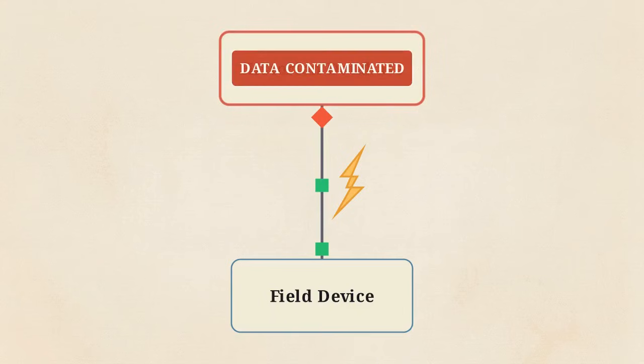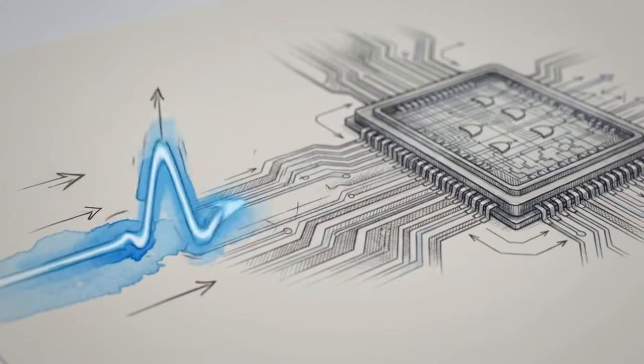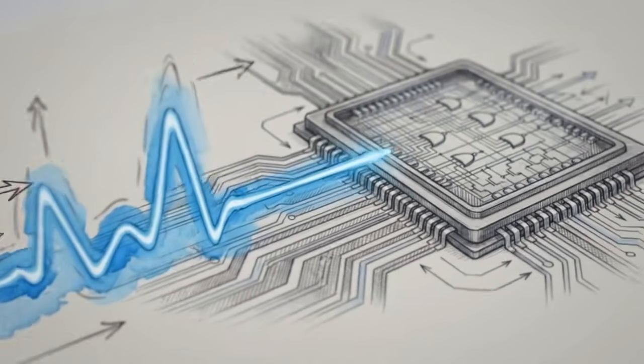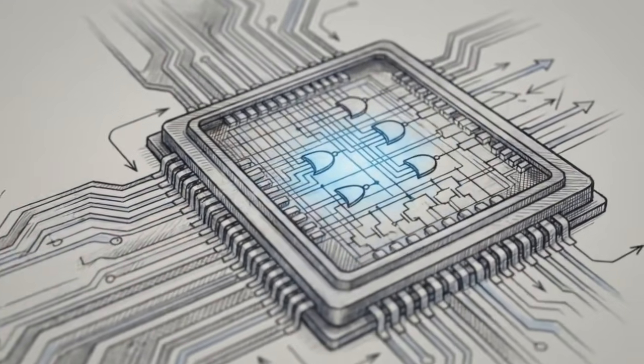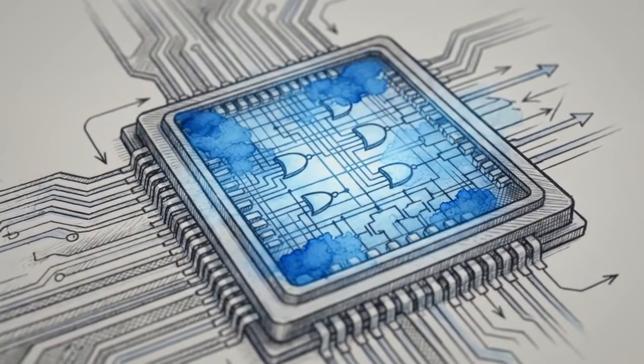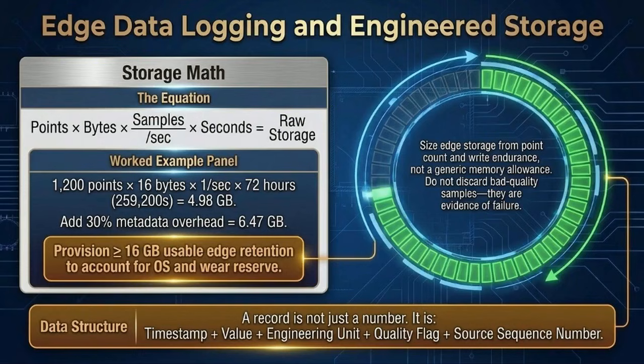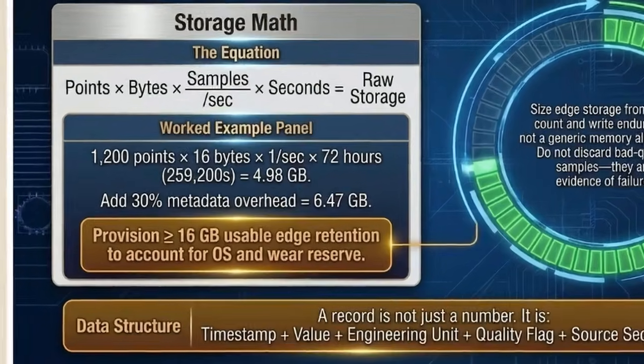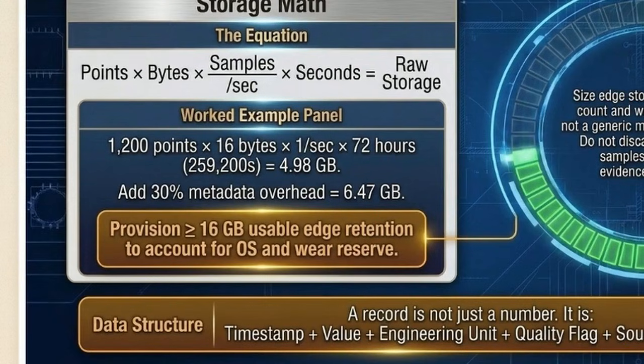At Layer 3, those protected raw field signals reach the edge controller, where they are converted into structured digital records. This panel defines edge data logging. A certifiable record must contain a timestamp, value, engineering unit, quality flag, and sequence number. The storage math example shows an edge controller must buffer 72 hours of data, requiring 16 gigabytes of storage to prevent loss.